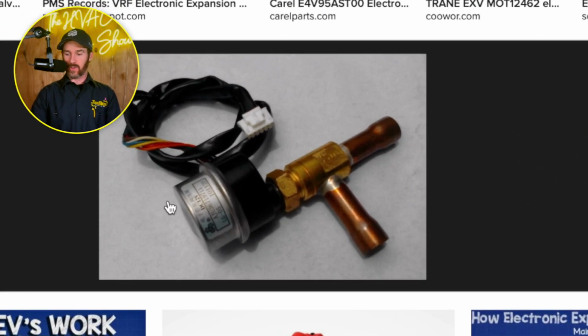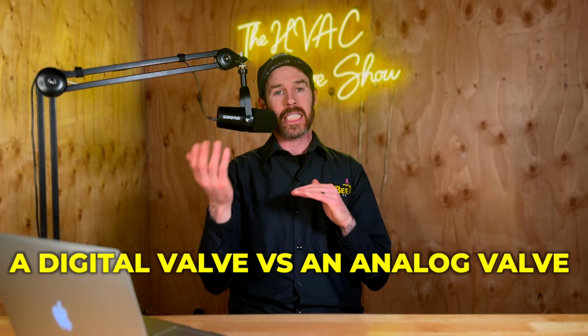The benefit of an electronic expansion valve, or EXV, is that you can think of it as a digital valve versus an analog valve. And so this system is communicating with the outdoor unit. When the system kicks on, it sends a signal to the outdoor unit, the thermostat and the furnace, and it tells the electronic expansion valve to open this much, and then open this much, and then open a little bit more. And it gradually pinpoints the exact amount of refrigerant that should be flowing into the coil. And so everything's working in unison. So when that compressor first kicks on, it's just barely pushing refrigerant into the coil. And that's how it maximizes that efficiency.